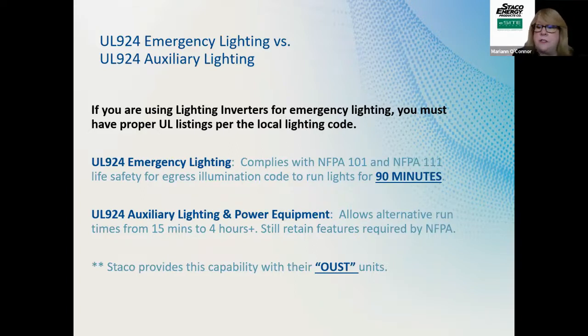What dictates the emergency lighting is the UL 924 rating. With the UL 924, what you do is you take the battery and the UPS and we get it certified for 90 minutes of runtime. And so some opportunities or applications call for a longer or shorter runtime. So there's auxiliary lighting, and what we can do is change the battery out and provide that longer or shorter runtime, and still maintain the features required by the NFPA, the fire agency. We can also accommodate that with our oust units. So you have an application and you need 4 hours runtime, but you still need that life safety feature. We can definitely provide that. Next slide.